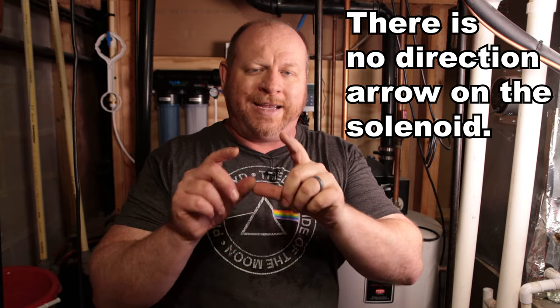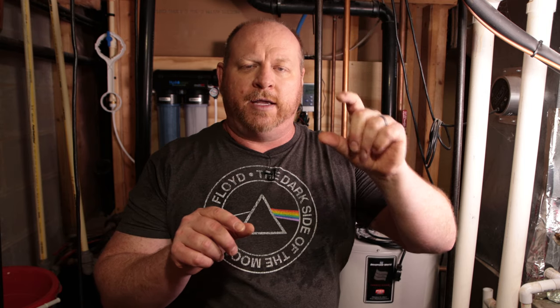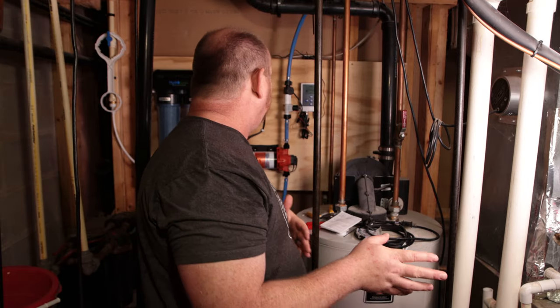And in doing so, I actually had the solenoid valve flipped. So you want to make sure that when you install it, that you have the solenoid installed so that there's a screen inside in the end of it. You want to make sure that the screen is facing towards the flow. So however the flow is coming, you want to make sure that the screen is facing it, which makes sense because the screen will keep stuff out of the solenoid valve. So all that is taken care of.